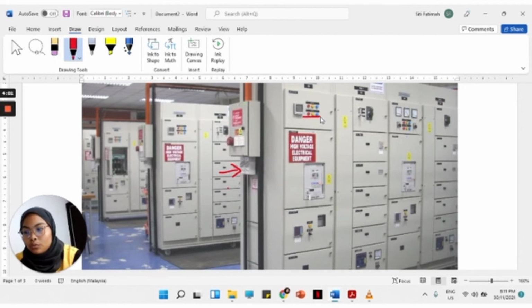Then, to connect the ACB into the busbar, first we have to use the charging handle and insert it into this slot, and turn the handle clockwise until it shows isolated, then continue turning the handle until it changes to connected.